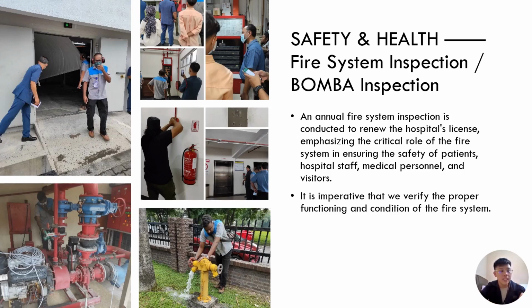As we can see, the bomba officer will visit the gen set room, and we check the main fire panel systems, and we will perform the triggering. We will trigger the alarm to test whether it is functioning.